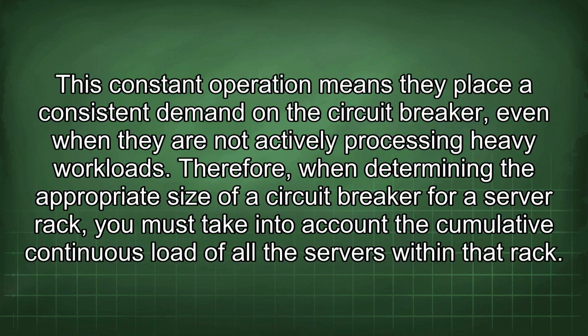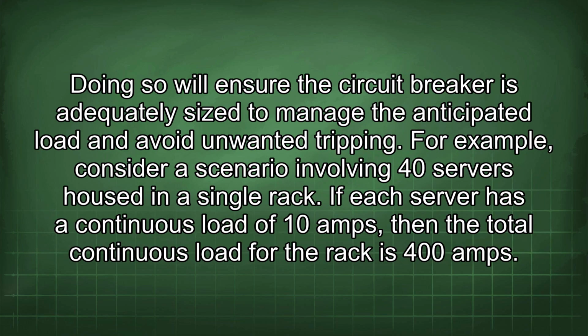the week. This constant operation means they place a consistent demand on the circuit breaker even when they are not actively processing heavy workloads. Therefore, when determining the appropriate size of a circuit breaker for a server rack, you must take into account the cumulative continuous load of all the servers within that rack. Doing so will ensure the circuit breaker is adequately sized to manage the anticipated load and avoid unwanted tripping.